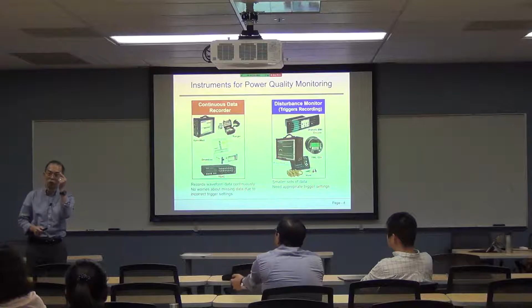And then at the end, when it arrives in your computer, you have to sort through what you're trying to find. Now, this one here is called the Disturbance Monitor - it will only capture disturbances. Inside this disturbance monitor, there's an algorithm already living there that keeps watching the wave shape, and when the wave shape or amplitude exceeds some threshold, it will trigger a snapshot - basically like 2 cycles before and maybe 10 cycles after, typically.